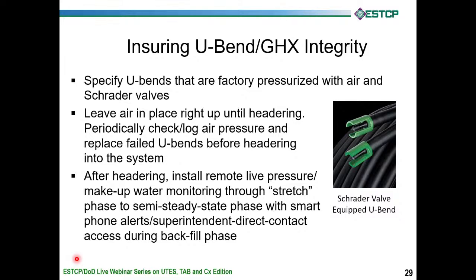The actual ASTM pressure test is only about a 4-hour test. And so you pump it up, you back the pressure off a little bit to stop the stretch, and then you monitor it for a short period of time. And we do that test for sure, but we also like to just continually monitor it before backfill started.